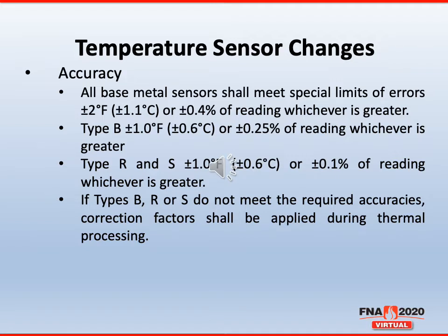all base metal thermocouples, no matter what their intended use is, shall be special limits of error. When it comes to type B, it's plus or minus 1 degree Fahrenheit or 0.6 degrees Celsius or 0.25% of reading, whichever is greater. And for types R and S, it's plus or minus 1 degree Fahrenheit, 0.6 degrees Celsius, or plus or minus 0.1% of reading, whichever is greater. But if you do have a type B, S, or R sensor that does not meet these required accuracies, then those correction factors shall be applied during all thermal processing.